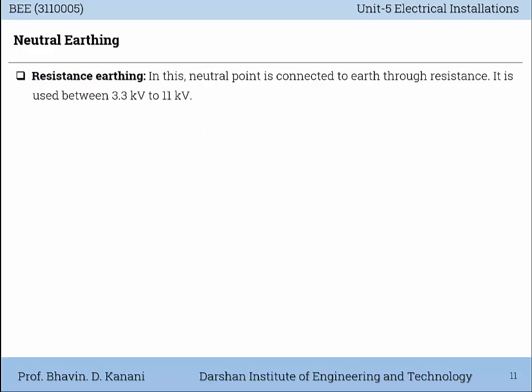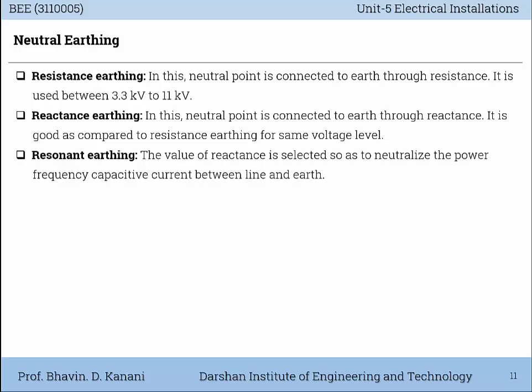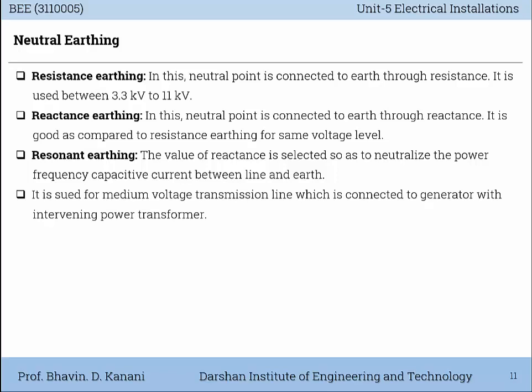Next is resistance Earthing. In this method, the neutral point is connected to the Earth through resistance. It is used between 3.3kV to 11kV. Next is reactance Earthing. In this method, the neutral point is connected to the Earth through reactance. It is comparable to resistance Earthing for the same voltage level. Then there is resonant Earthing, where the value of reactance is selected so as to neutralize the power frequency capacitive current between line and Earth. It is used for medium voltage transmission lines connected to a generator with an intervening power transformer.